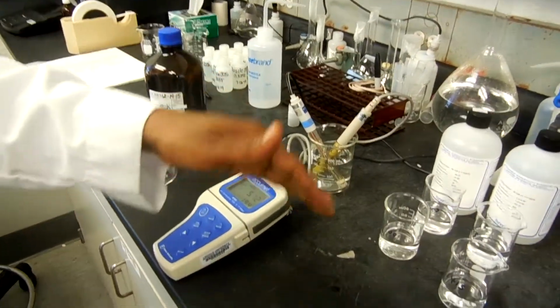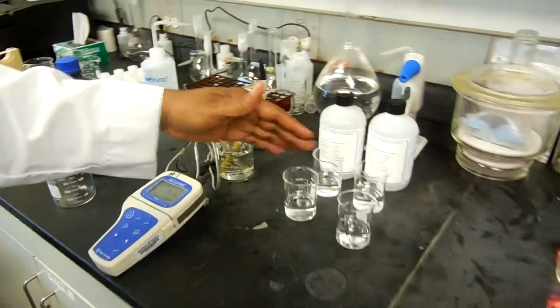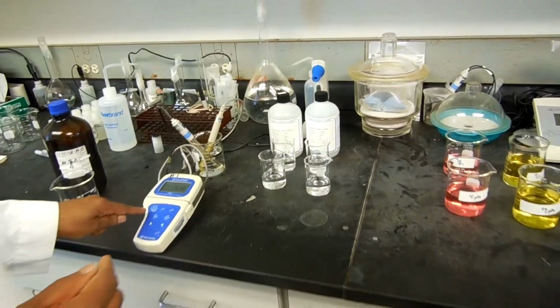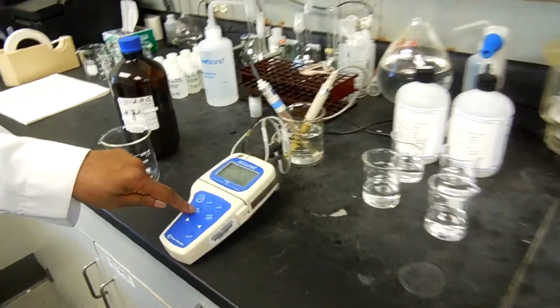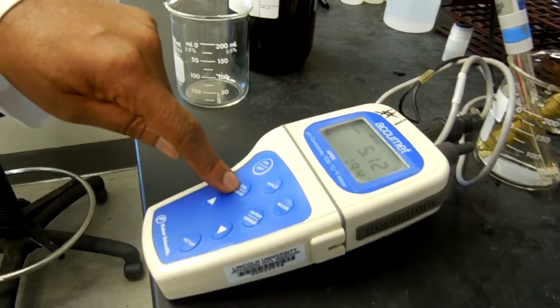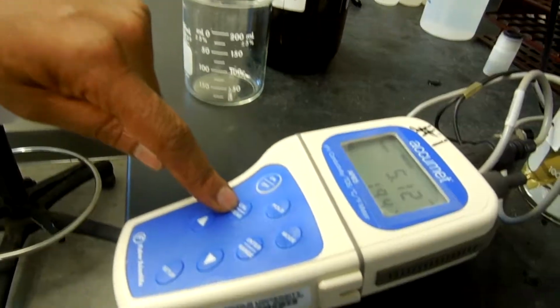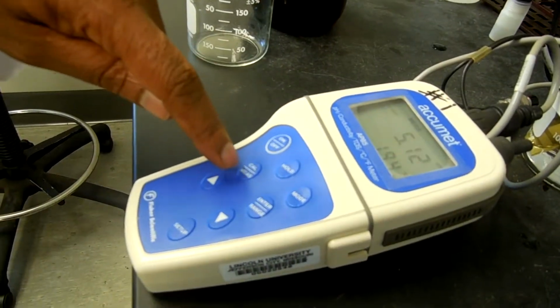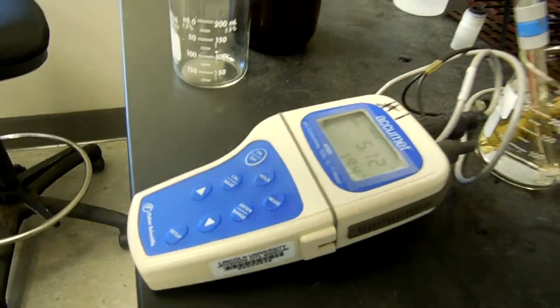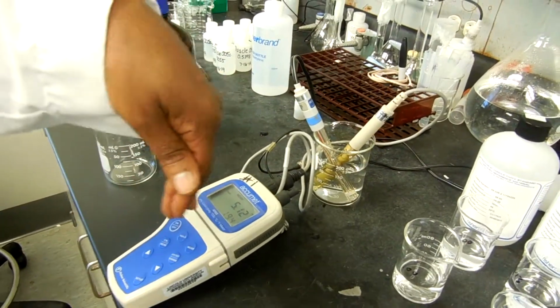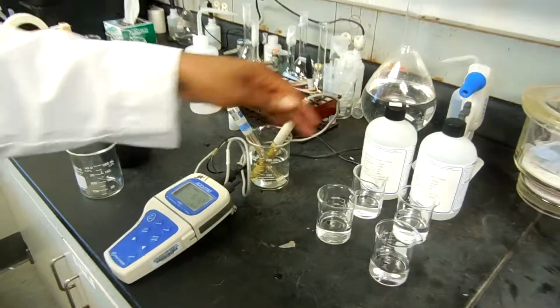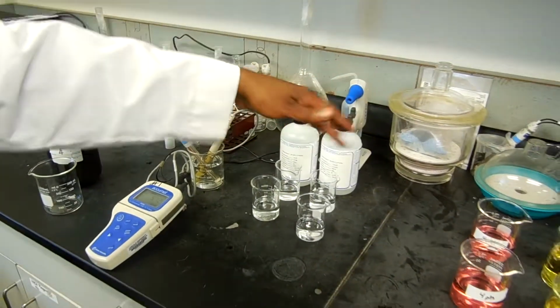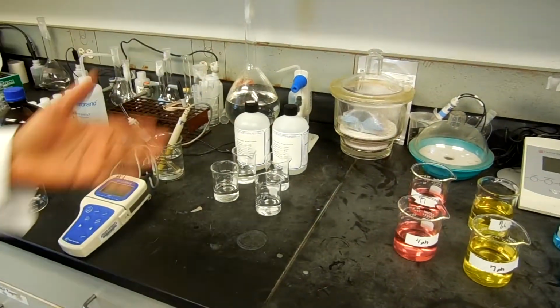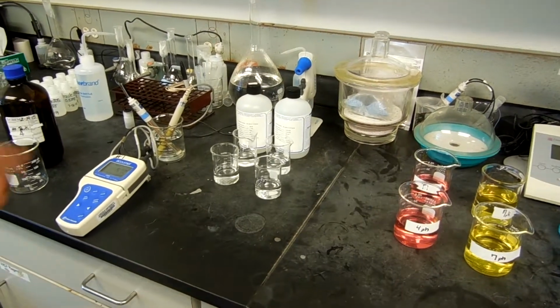One important thing: once you've done the calibrations, you can validate by going to the measure mode. This is the calibration button here. When you place each of the electrodes, you do calibration, and then after that you press to go back to measure. So you can validate by checking your instrument, whether it's okay, by using another set of similar solutions, but from a different manufacturer or different vendor.